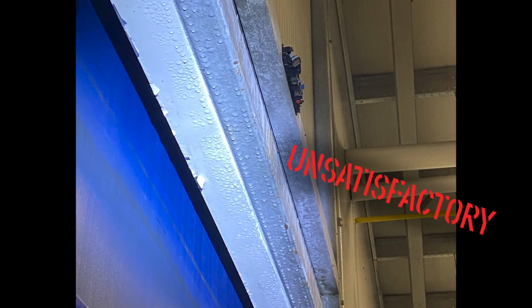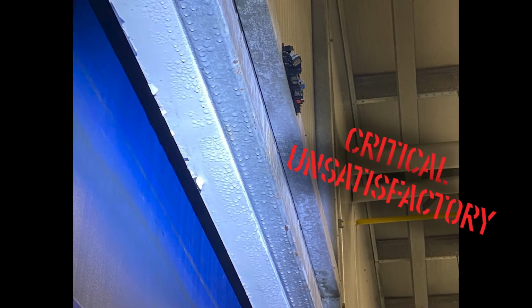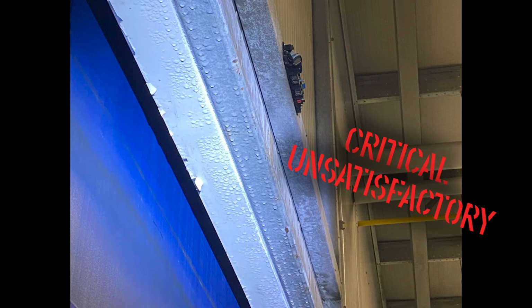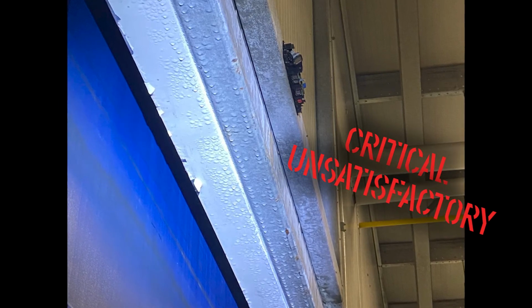Here is another example of condensation, this time on the framework of the door leading out of the cooler. This area is likely to drip on any product passing in or out of the cooler, significantly increasing the likelihood of contamination. This condensation is an unsatisfactory finding in a critical area and must be addressed before the cooler is used for the day.